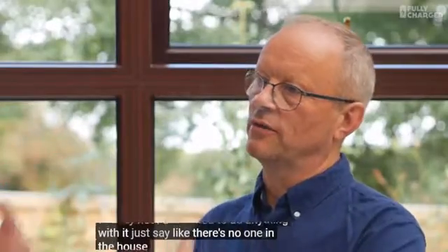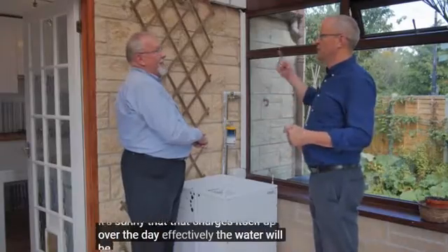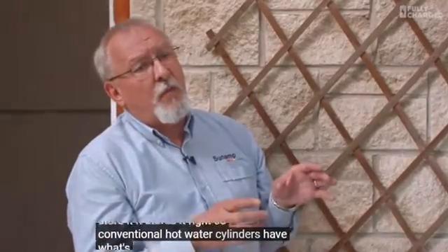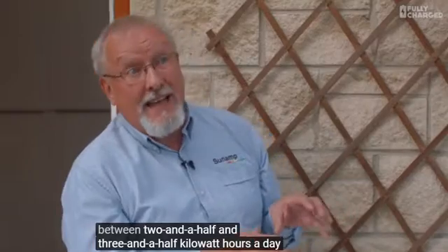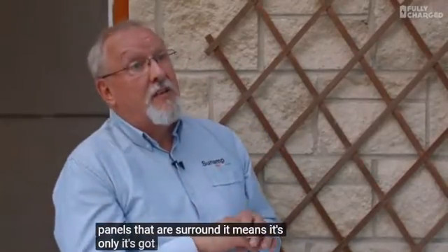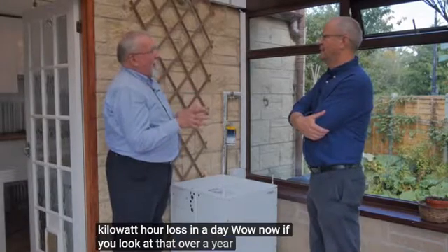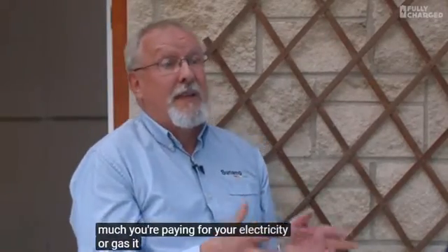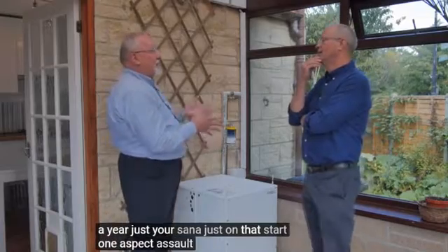When there's no one in the house and it's sunny, it charges itself up over the day. It does store that heat. Conventional hot water cylinders have a standing heat loss of somewhere between two and a half and three and a half kilowatt hours a day. This, because of its vacuum insulation panels, has less than 0.6 of a kilowatt hour loss in a day. Over a year, just on standing heat losses, depending on how much you're paying for your electricity or gas, that could be saving somebody something like £100 a year - just on that one aspect.